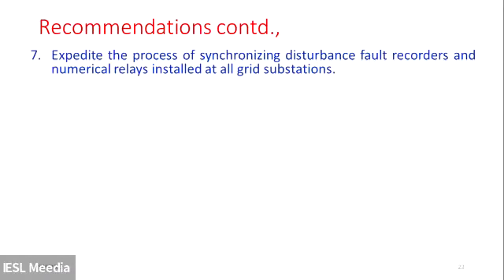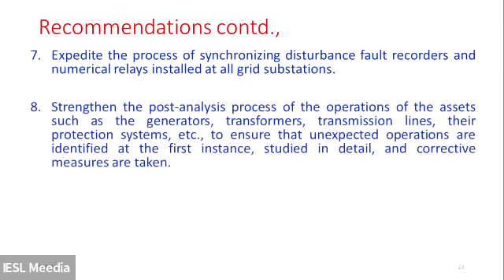And then the 7th recommendation: expedite the process of synchronizing disturbance fault recorders. Now, this issue has been there even in the previous committees. We have made recommendations on that, because there is no point in having DFRs if their clocks are not synchronized. One can argue, of course, that we can do it manually, but I don't think that we can reach the time resolution required to do a deep analysis unless you have synchronization. Then the post-analysis process of the operations of assets, generators, transformers, transmission lines, and their protection systems, etc. We recommend to strengthen that procedure.